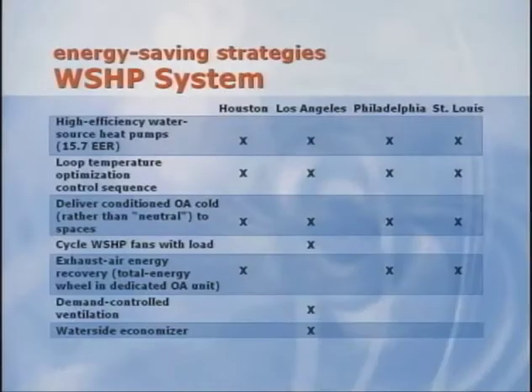At times during the year, some heat pumps in the building may operate in the cooling mode, while others simultaneously operate in the heating mode. The heat rejected to the water loop by the heat pumps that are cooling helps keep the temperature of the loop warm enough to provide heat for those heat pumps that are in heating. This is a form of heat recovery during these times. Both the cooling tower and the boiler can be shut off, saving energy. For each of the 4 locations, high-efficiency heat pumps were used. Also, a loop temperature optimization control sequence was employed. More on that in a moment.